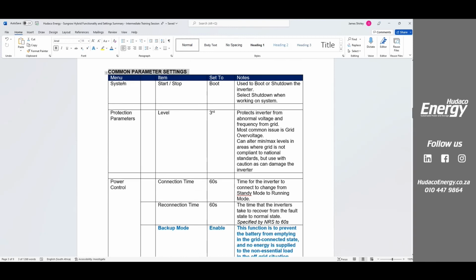So the first one on the menu is system. There we can start and stop, which is basically the way we can turn the inverter on or off from the AC side. Obviously, sometimes people just shut down the breakers and the inverters and the batteries, and that's okay. But the best way to do it, just like you would shut down your computer instead of suddenly turning it off, is to actually go and shut down. What it does is when you turn it back on again, it goes through the startup routine properly and resets all the cache information. The next one is protection parameters.